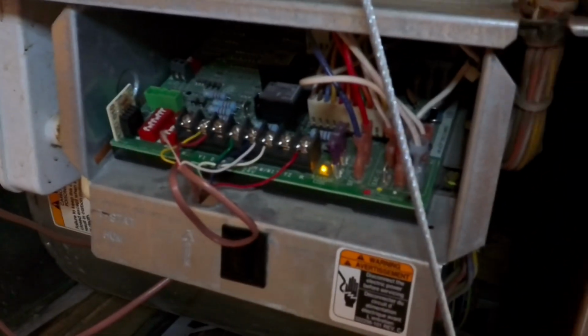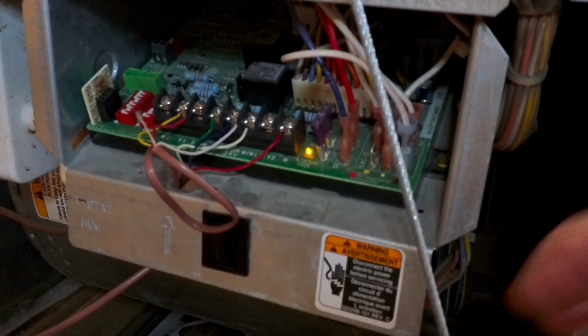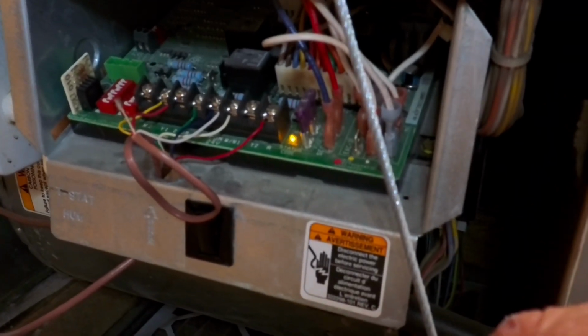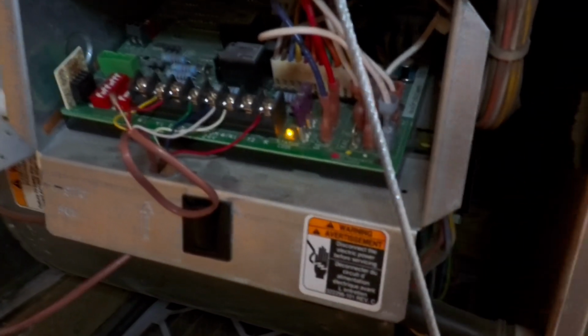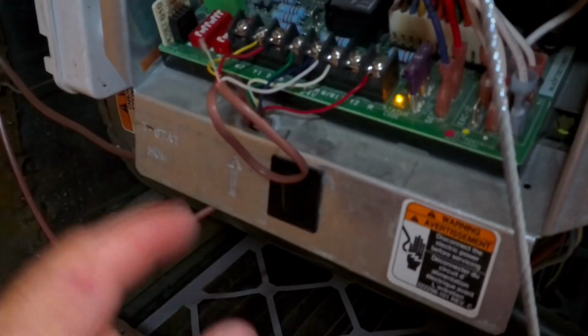Now, the thing to know about a furnace is most furnaces have a transformer built into it. Ours is located right here behind the system. So 110 volts comes into the transformer. The transformer is a step down transformer, so it steps the voltage down to 24 volts AC. And that's what our thermostat wires are running at. They're running at 24 volts.